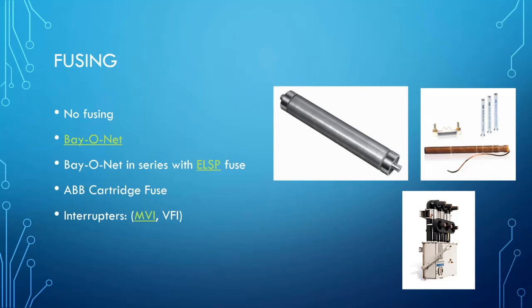At certain KVA ratings, especially if there's a 4160 volt primary, the ampacity becomes too much for a Bay-O-Net fuse and even an ELSP fuse. And in that case, we go to ABB, which has some high ampacity cartridge fusing systems that they sell to all of the transformer manufacturers. Or we go to some sort of interrupter, an MVI or a VFI. These are products that are vacuum bottles that are compact.